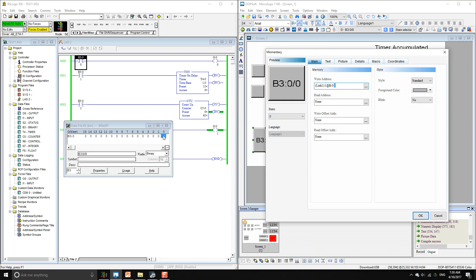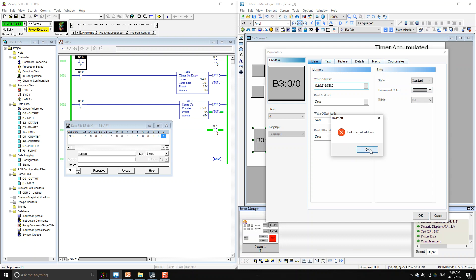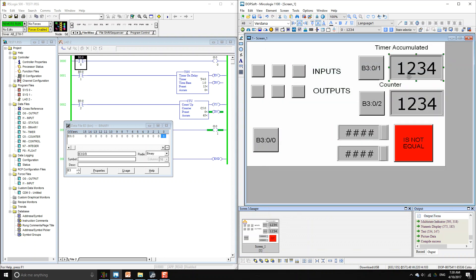The bit is zero. This is a momentary button so it only works with bits — if you try to use a word it will give you an error. For numeric entry you can use words, but for buttons and indicators you have to use a bit address. So that was for a bit: binary word zero, bit zero.